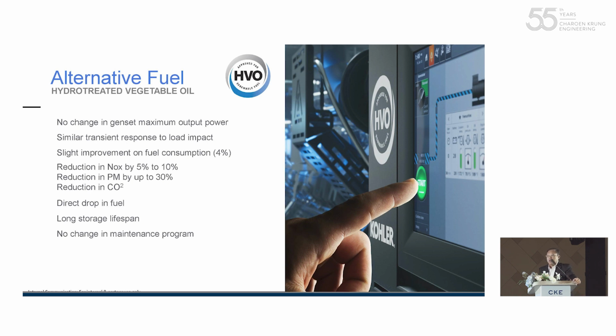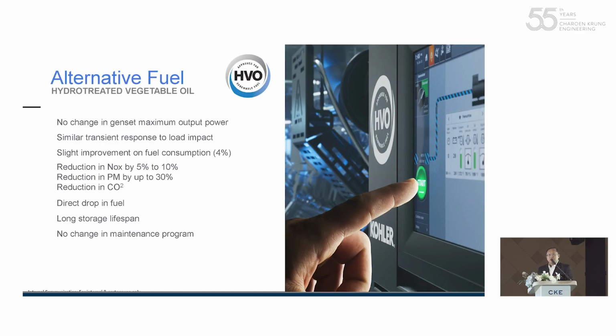This is unlike biofuel. Biofuel and fossil fuel have a disadvantage in terms of oil aging, so the fuel needs regular maintenance—you need to pump it out and clean it every 6 months or so. But for HVO, it's zero maintenance. You can store it in the fuel tank for more than 10 years and it will still work as is.